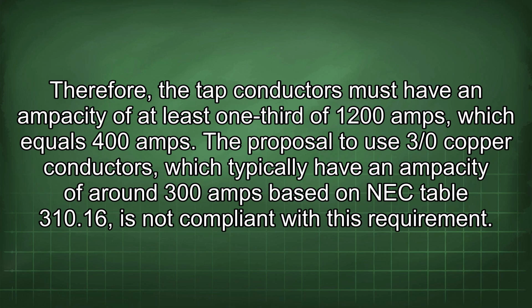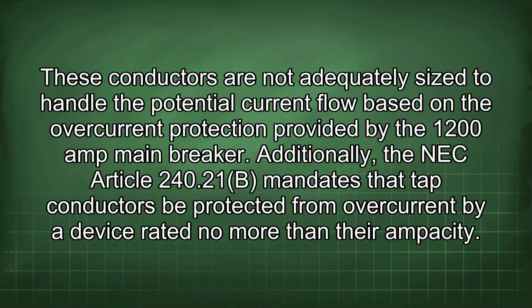The proposal to use 3/0 copper conductors, which typically have an ampacity of around 300 amps based on NEC Table 310.16, is not compliant with this requirement. These conductors are not adequately sized to handle the potential current flow based on the overcurrent protection provided by the 1200 amp main breaker.